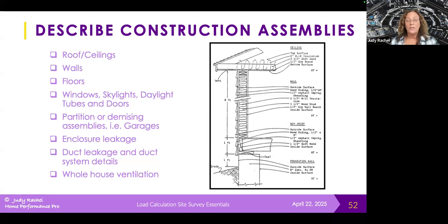And then if we have a whole house ventilation system, so not our intermittent exhaust systems, such as the kitchen exhaust fan or independent intermittent bathroom fans, I'm not talking about those source control, but when we have a whole house ventilation system, whether that is using exhaust, supply or a balanced system, bringing in outside air or causing the exfiltration of our conditioned air because we're using an exhaust only system, it is going to affect our load calculation, and that also needs to be put into the load calculation.